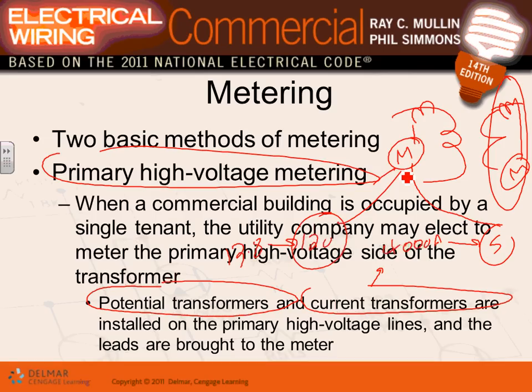So what they do is they have a transformer that converts the voltage into 120. Now they can sense the 120 and proportionally reflect what this voltage is. And the same thing, the 4,000 amp, they have a CT transformer that converts it back to 5. So if the system has a 4,000 amp, the meter only sees 5 amps. If we're pulling 2,000 amps, the meter will see 2.5 amps.